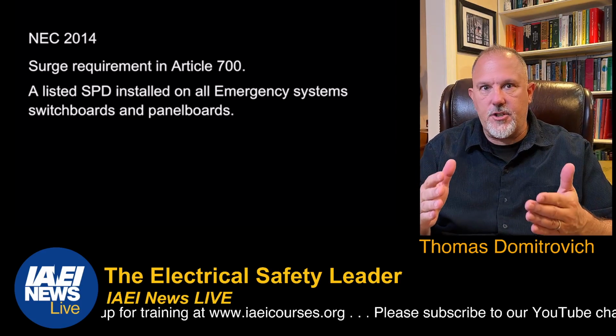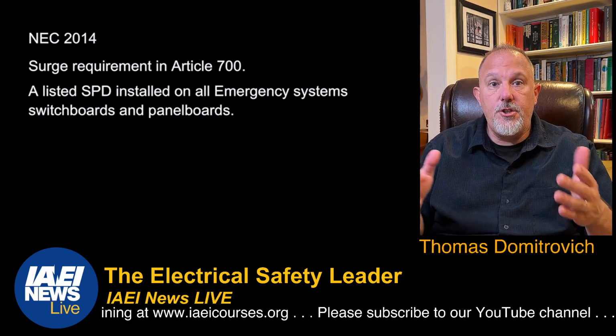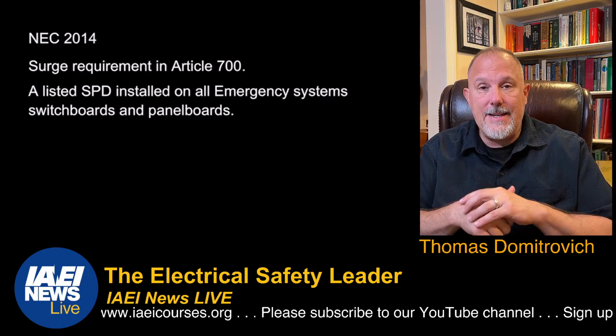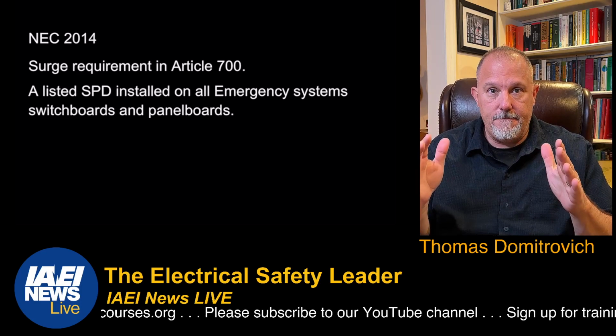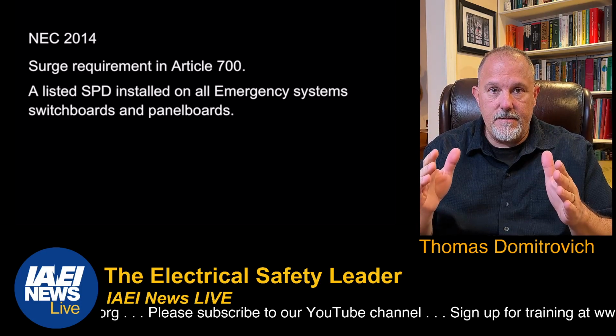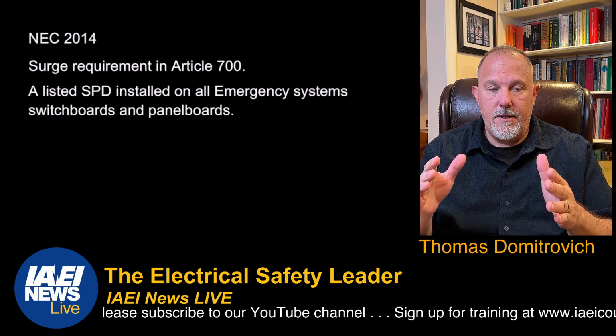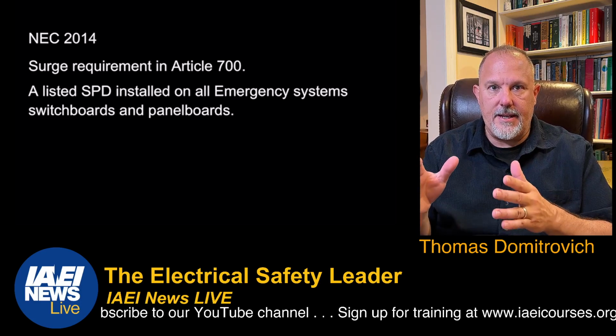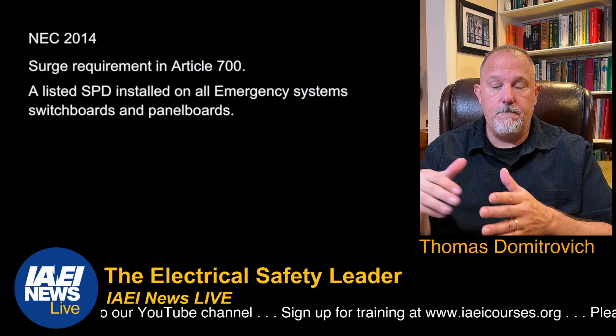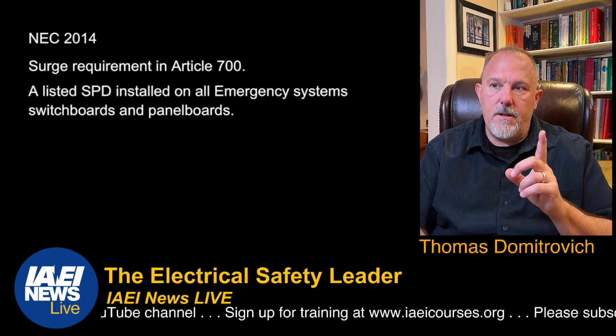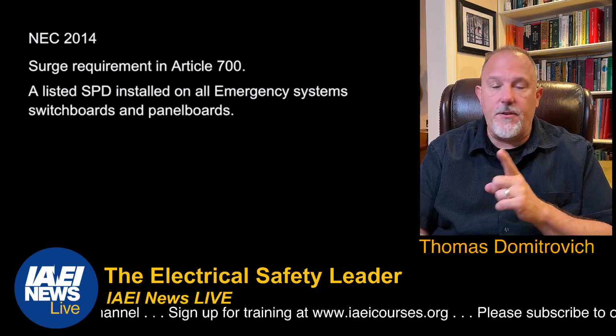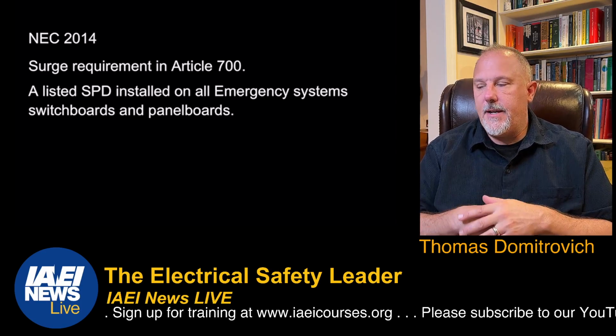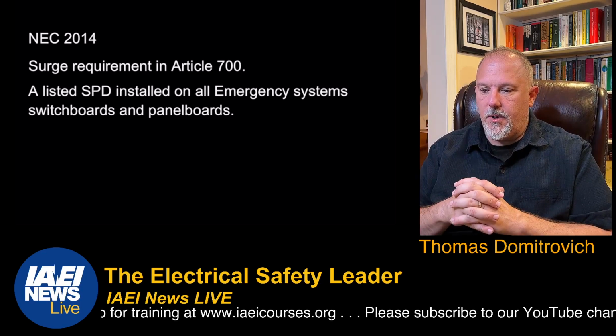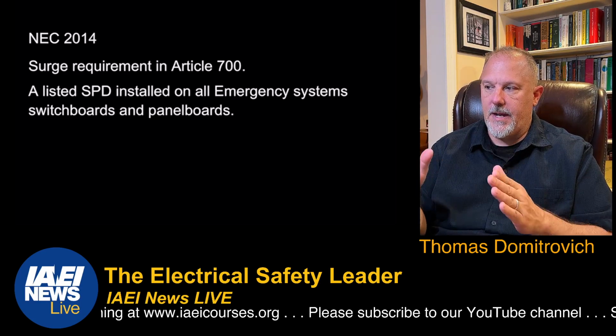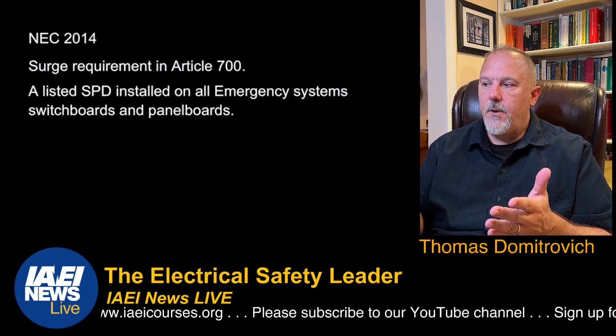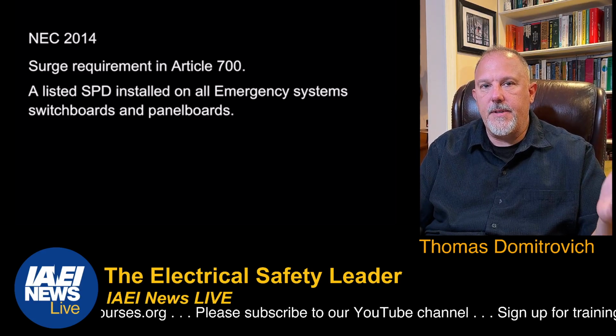So if I can demonstrate a significant amount of loss due to electricity, the NEC covers that. I don't have to kill somebody. That's a fallacy. I don't have to kill someone to have a requirement in the NEC. I'm limiting damage to equipment as well. So when this went into Article 700 in the 2014 code, I explicitly remember trying to figure out how do we address the substantiation when we're hampered by the data that we're using.